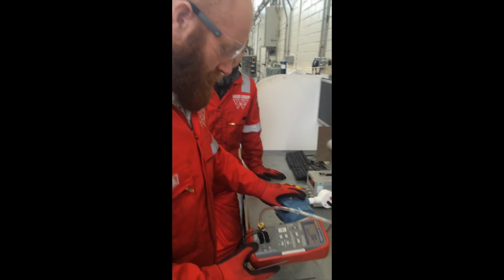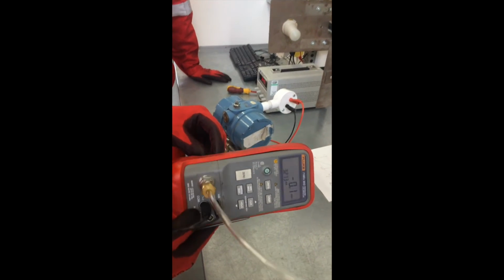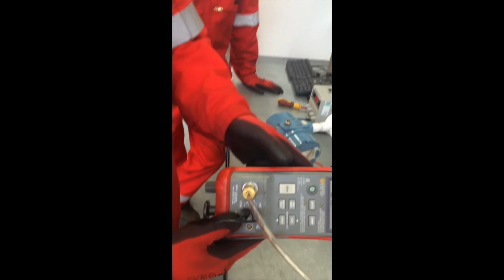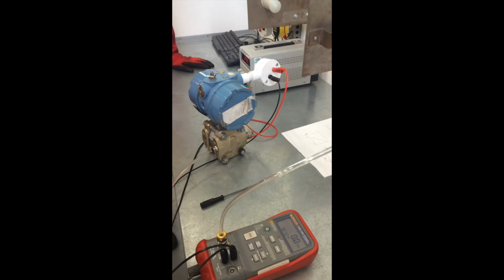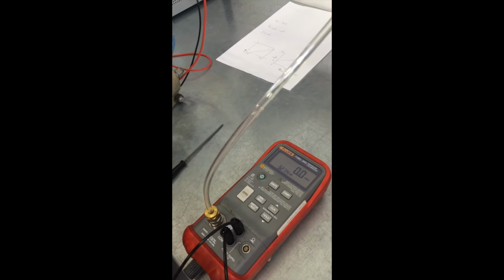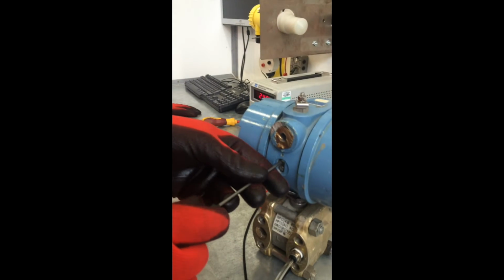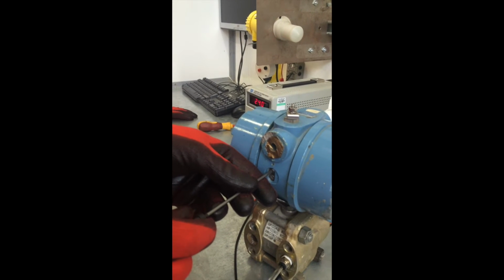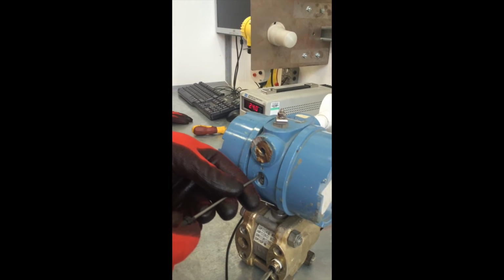To calibrate the DP cell, we have to release the pressure from the pressure calibrator. Again, as before, you release it from there and then shut that back over, and make sure it's at 0 by pressing the 0 button. Okay, so as you can see, the reading is out. To change the reading so that 0 millibar gives 4 milliamp, look for the zero screw and adjust it. You're adjusting it by turning it clockwise, and as you can see, the value starts to rise. We look to bring it to 4 milliamp.